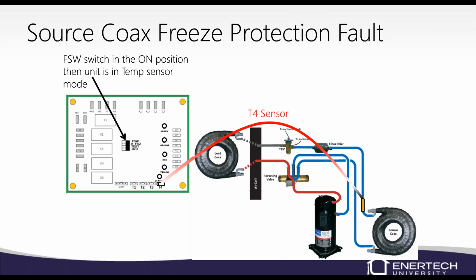One thing I want to note real quick, if you get a source coax freeze protection fault, it could be a refrigerant issue, low on refrigerant, or an expansion valve stuck closed, or it could be a water flow problem because we're looking at refrigerant temperature. If you don't have proper water flow, it's going to drive our suction down and give us low pressure. So that's what that T4 is looking at. It's looking at refrigerant temperature.